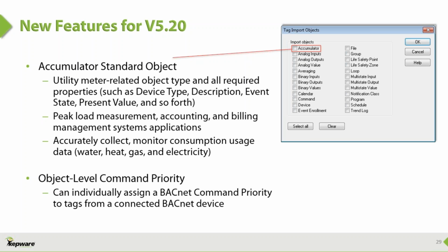Quick example, maybe your BACnet fire suppression systems need to override a standard operation of an air handler in the event of a fire. Or maybe an air handler needs to be maintained, and prior to lockout, a technician wants to manually shut this down to override the HVAC system. These changes, we hope, would provide the operator the ability to designate command priorities at an object level. This would result in increased productivity, workflow efficiencies, and certainly in safety.